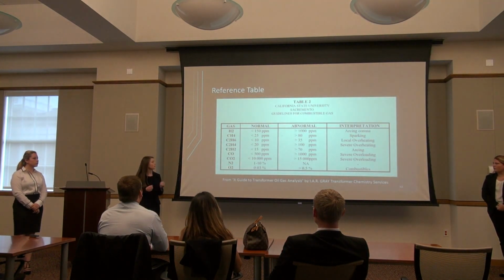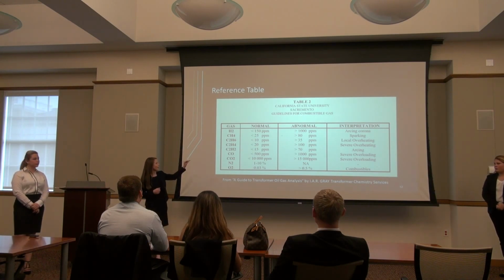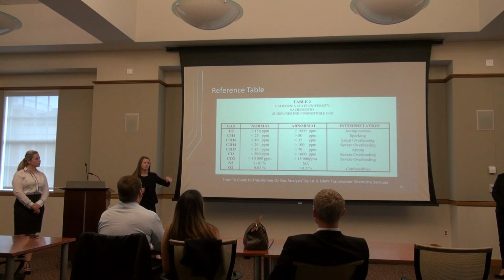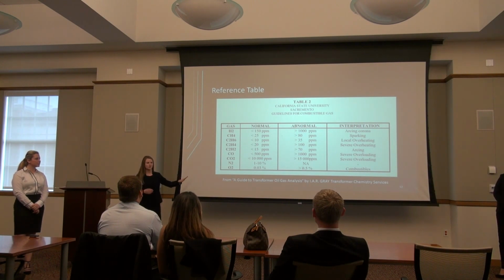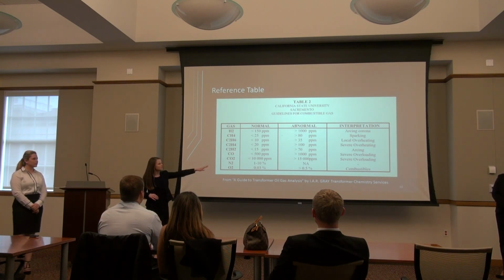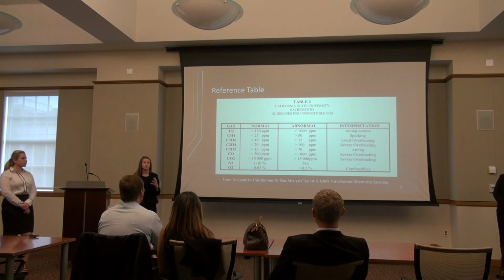Okay, so this is the reference table for our first analysis. So what you're seeing here is for each gas, there's a normal and an abnormal range. And we want the gas to be in the normal range. If it's in the abnormal range, that means danger, warning, watch this transformer because it could explode. That's a little extreme. But if you see the interpretation on the far right-hand side, that does tell us the problem that is most probably occurring within the transformer at that time.